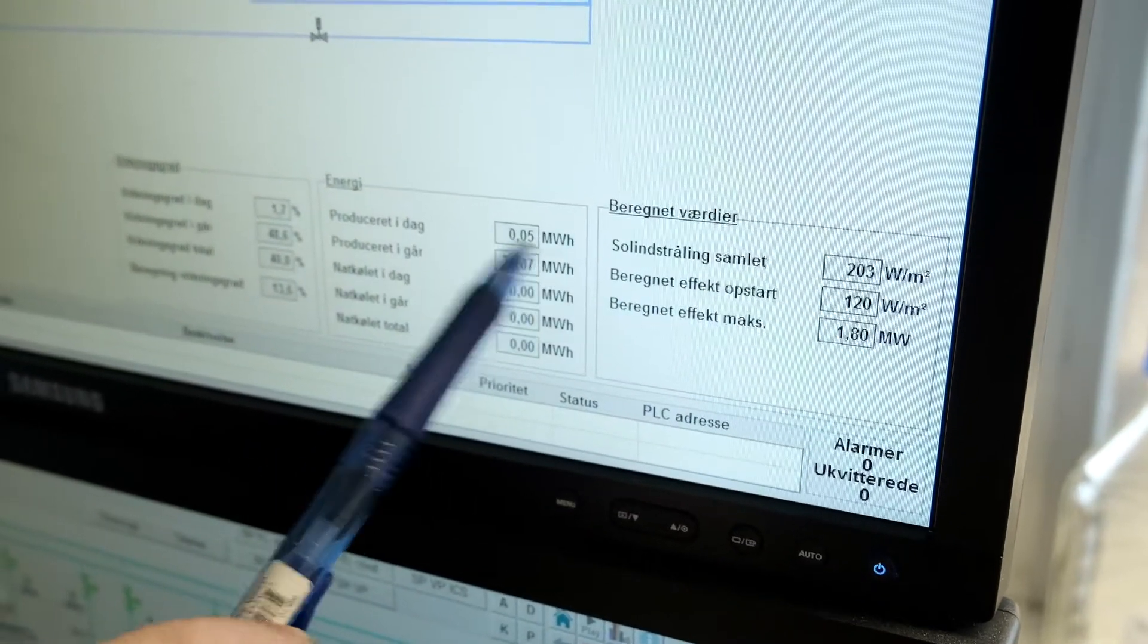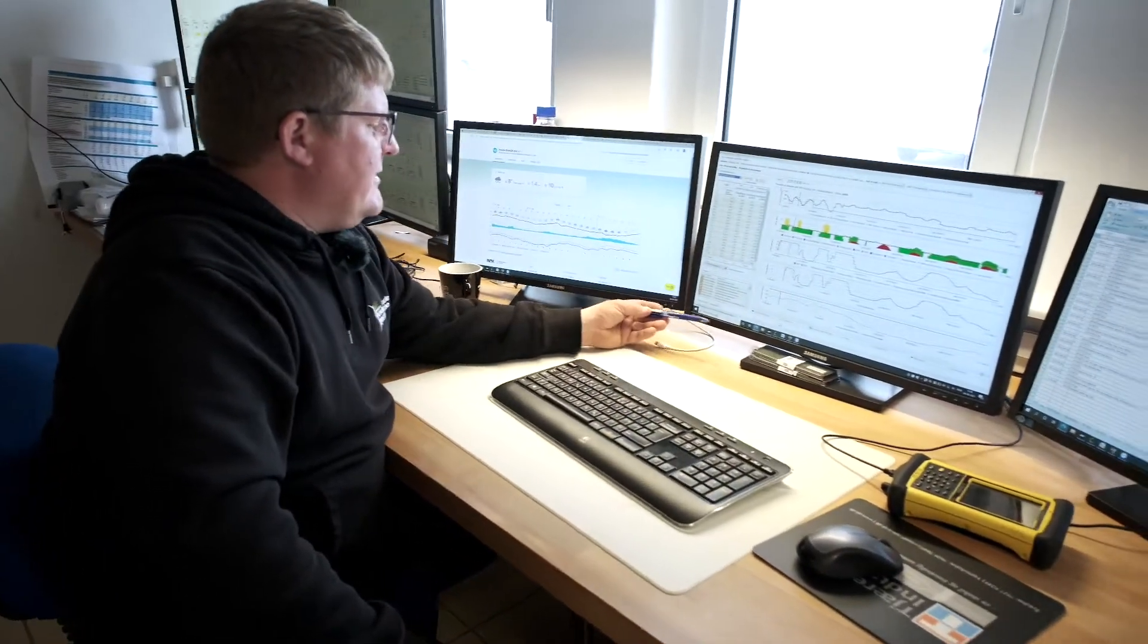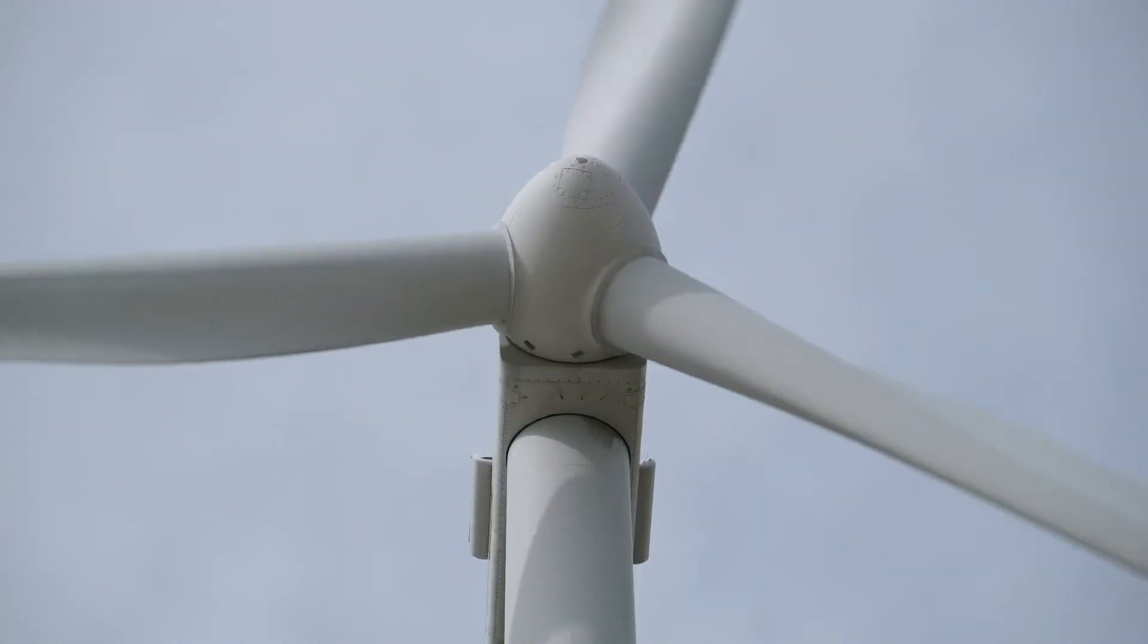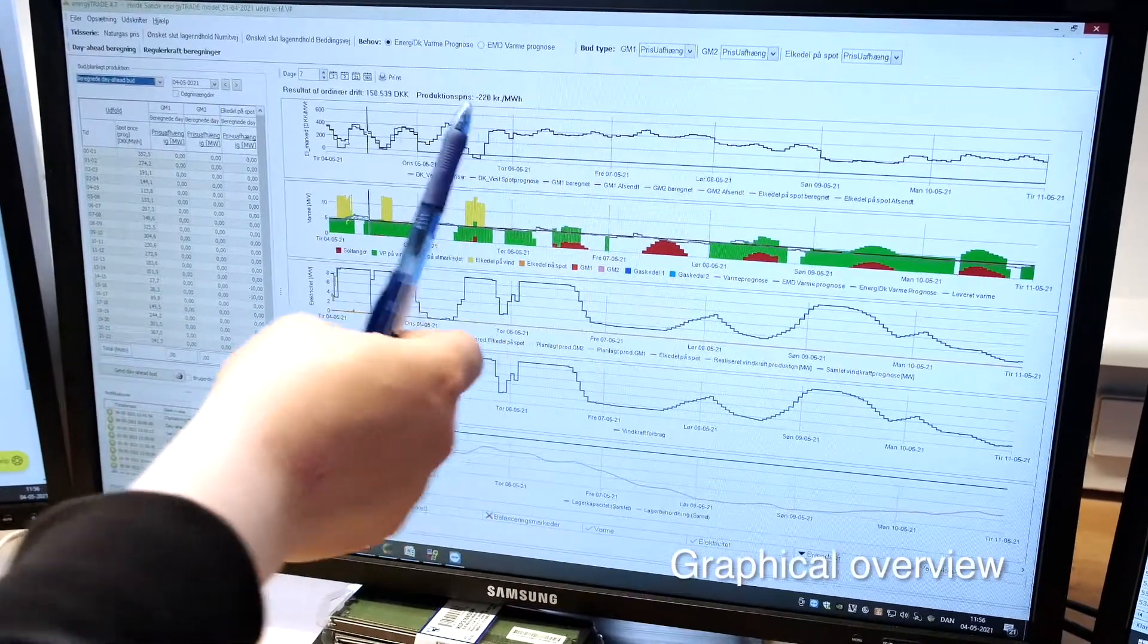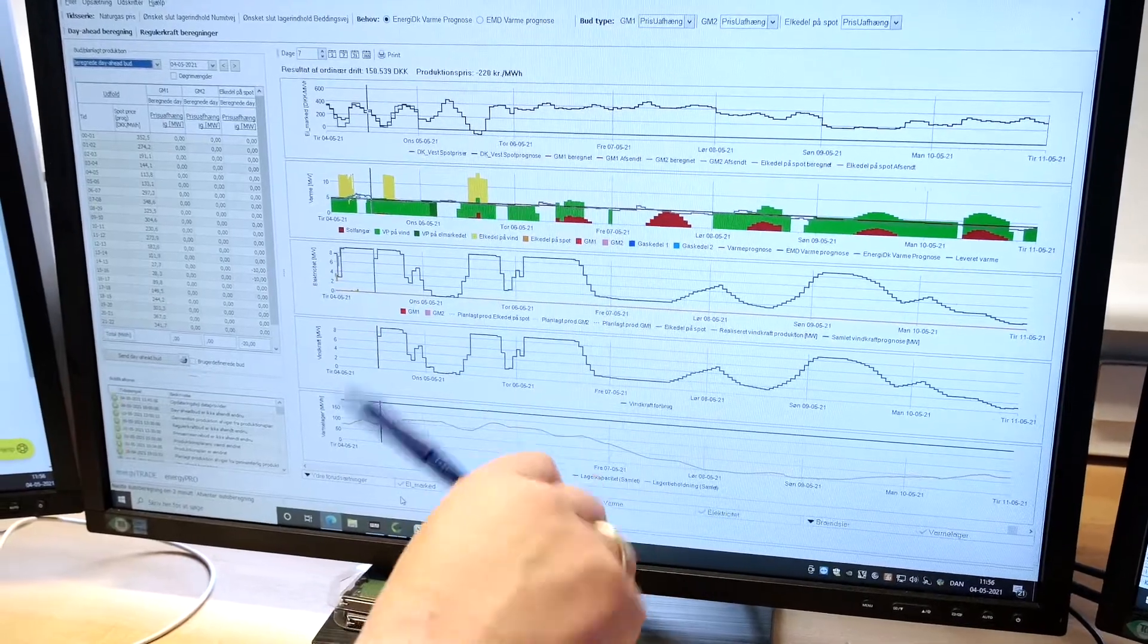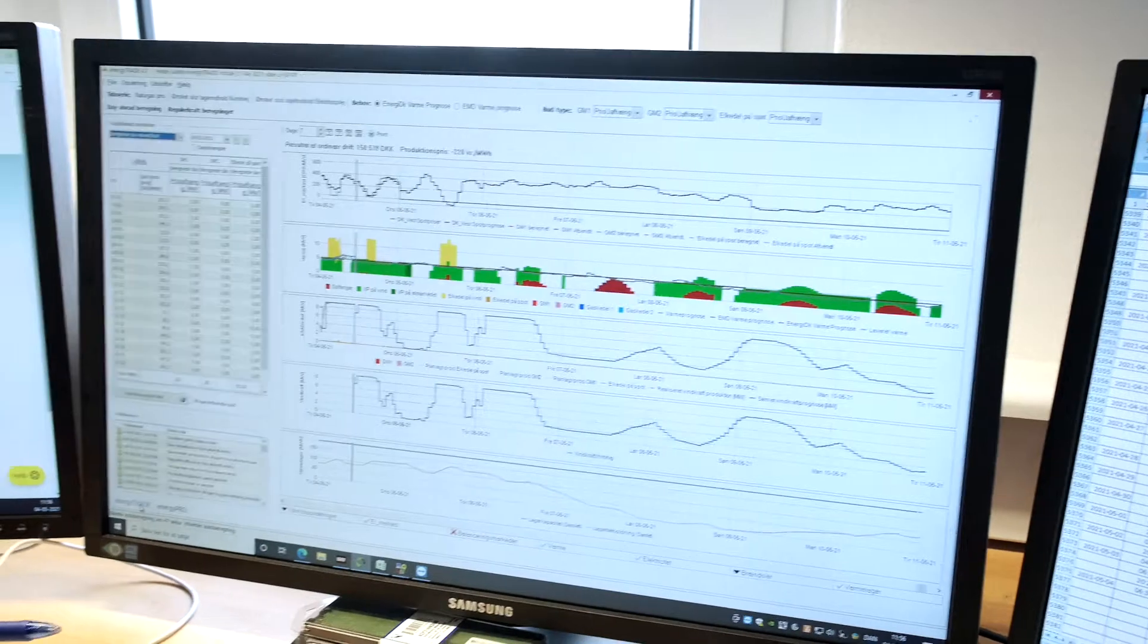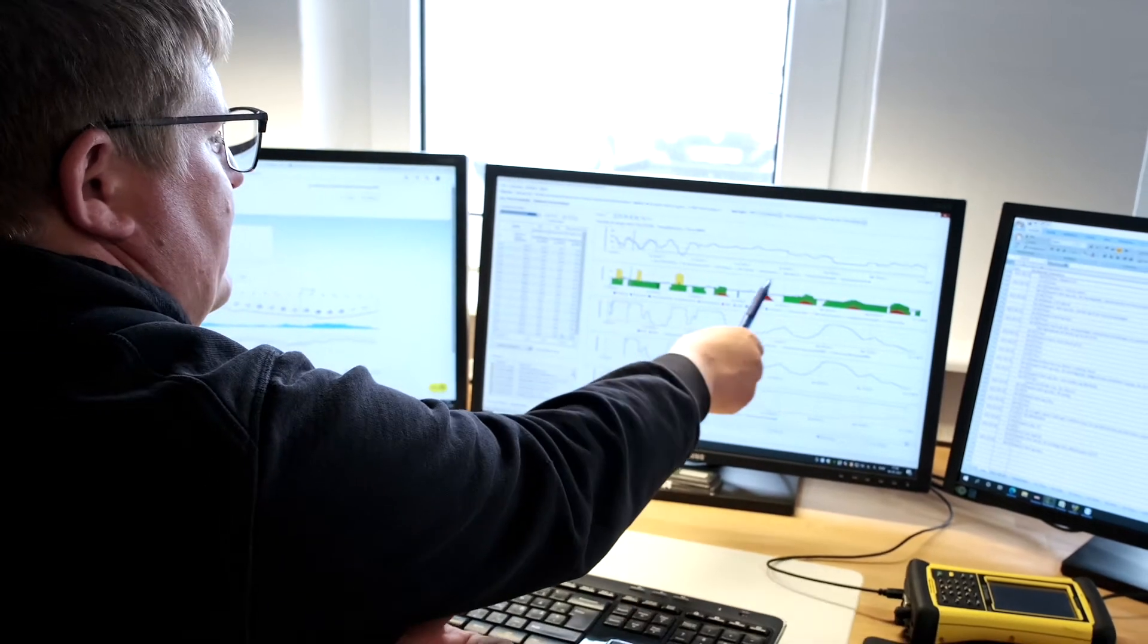The way we do it is we're looking into the energy trade software that has been developed by EMD in Aalborg. As you can see, we are following the prognosis of the spot market, the electrical price hour by hour. Then we're looking at how much wind there is, which is converted into electrical power, and how much solar production we have. The energy trade module uses this model to figure out what is best for us and how we are producing the cheapest heat seven days ahead.